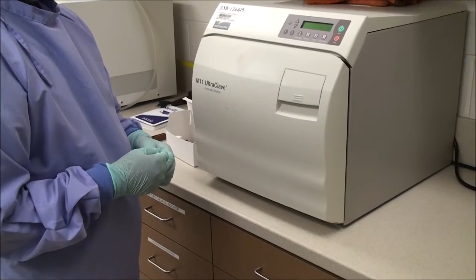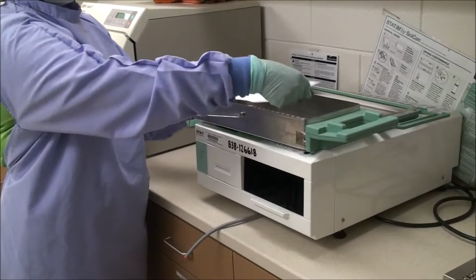To drain water, open autoclave. Pull the hose down, and let the water drain into the bucket. Load Statim cassette loosely, do not overload. Close cassette lid until you hear a slight snap.